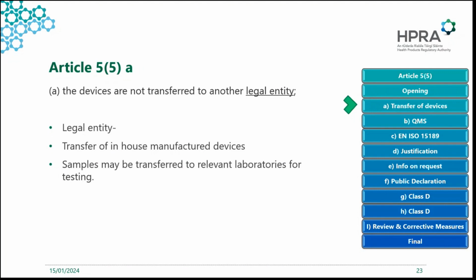And essentially that could be the output of Article 5.5a: a policy where you say we're not going to transfer them outside our legal entity. We've identified our legal entity, and then you just follow that procedure. You can transfer samples. So if you need to refer samples to a specialist laboratory that maybe has a specific in-house test or a specific area of expertise, you can send the samples. You just can't send the IVDs that you're making yourself. And that's to keep the IVDs in the organization that's producing them, because they're responsible for the in-house IVDs that they're creating. And also it's where the expertise lies. If you've created it, then you have the most expertise when it comes to actually conducting these tests.